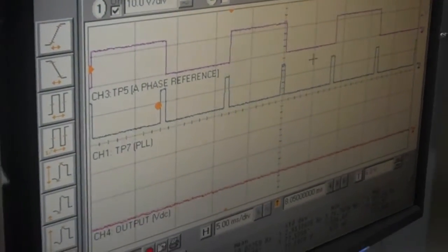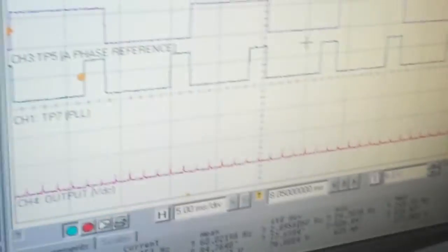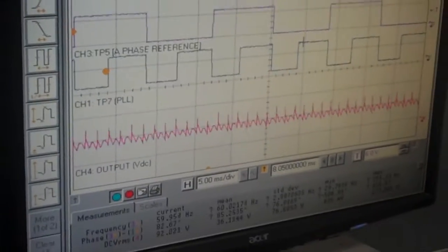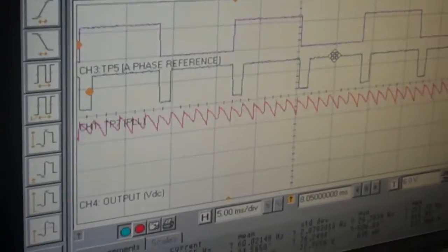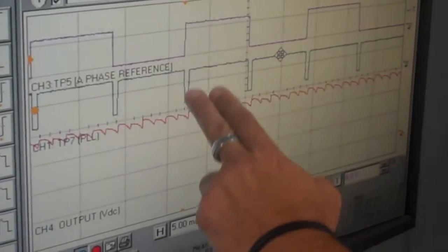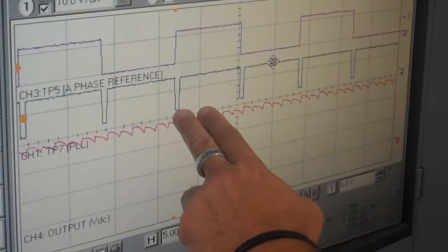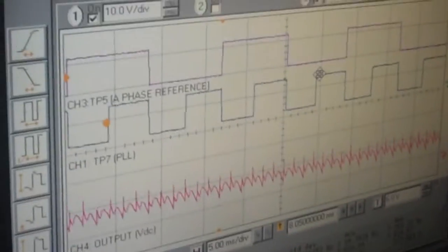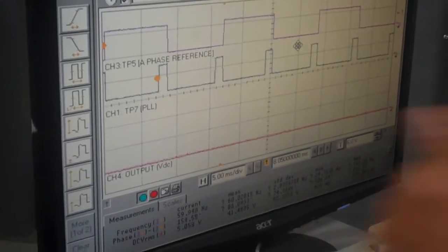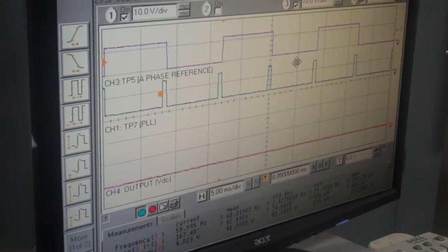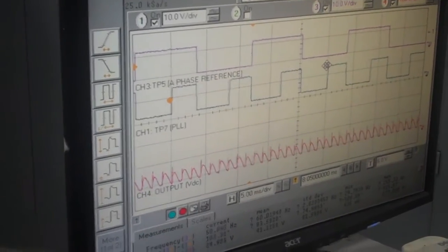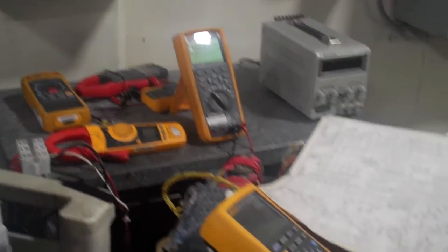And we basically go through the thing. We enable now, and we start bringing in SIG-high, and again we see the corresponding delay angle. This duty cycle increases from this edge. Go ahead, Tony, bring it back. Which is actually this right here, the trailing edge. We see the 12 humps, and we can see again that we have all the 6 SCR firing. Go ahead, Tony, bring it back again. So we are at 0, we're negative 4 volts, and when Tony gets to 6 volts DC of SIG high, we have the same 278 volts DC.